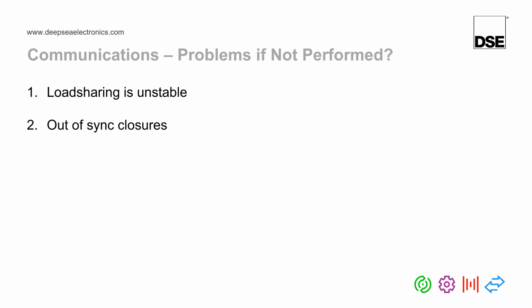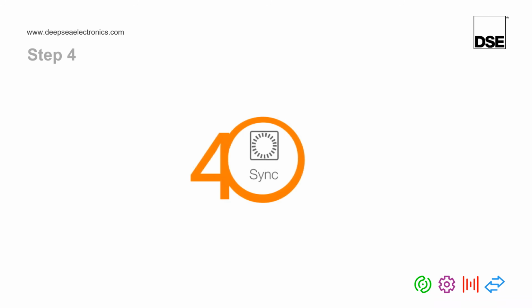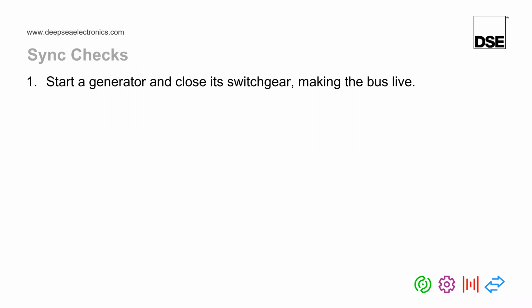Okay, we'll carry on now with the final part of the presentation, which is going through step number 4. Step number 4 is basically doing synchronizing checks across generator breakers to make sure nothing has been wired incorrectly. The way we're going to do this test, we're going to start a generator and close its breaker, making the generator bus live.